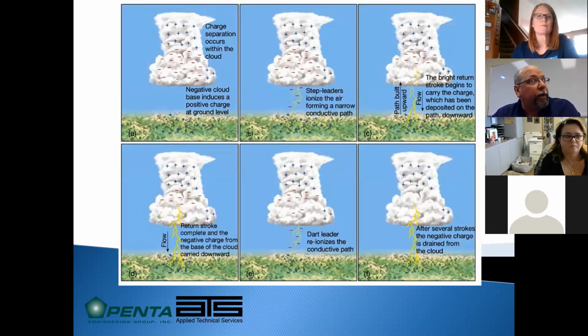So in general, as a storm cloud builds, there's a charge separation that occurs within the cloud. Negative and positive ions, and a negative cloud base induces a positive charge at ground level. So you end up with a lot of positively charged ions at the ground level. Step leaders ionize the air and they start to form a path to the ground. And as soon as that path is connected, then you have an energy exchange between the cloud and the ground. And that continues until those negatively charged ions have reached the ground, and the cloud then is no longer polarly charged.